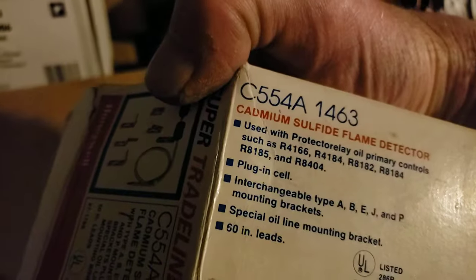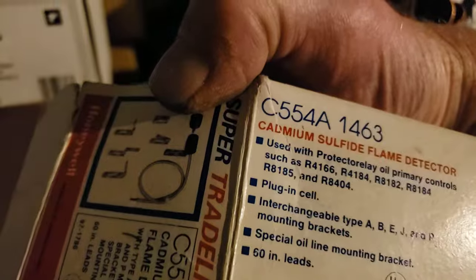I got home at 9 o'clock at night and I didn't have to call anybody — I was able to fix it myself. Here's basically what this is: it's a flame sensor, C554A 1463. This is the box for the old one. I actually just ordered another one just to have in the house. It's not going to go bad twice in one season, but it's not a bad thing to have.